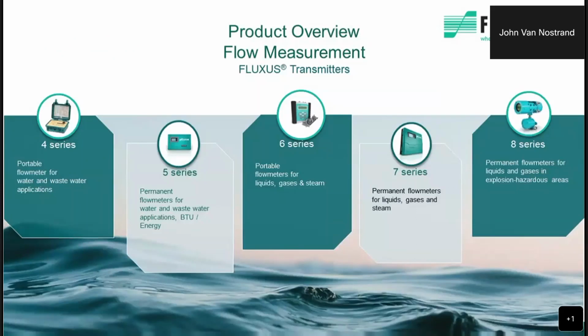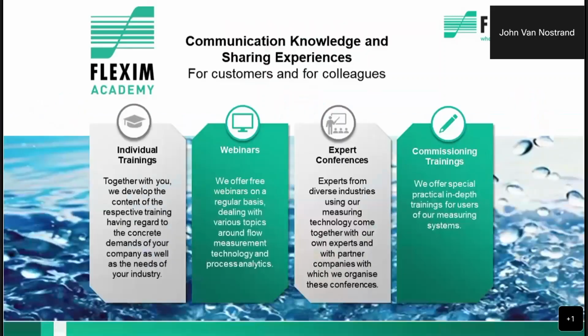FLEXIM manufactures a number of different meters. The 4 series and the 6 series are portable flow meters that can be carried out into the field to spot check, temporary service and verification of calibration of other meters, as well as semi-permanent installations. The permanent meters are the 5 series and the 7 series, and then there's an 8 series, which is a class 1 Div 1 meter. It's not often used in water wastewater applications, but I bring it up because there are sometimes in pump stations where there might be VOCs present, and that requirement could be there.